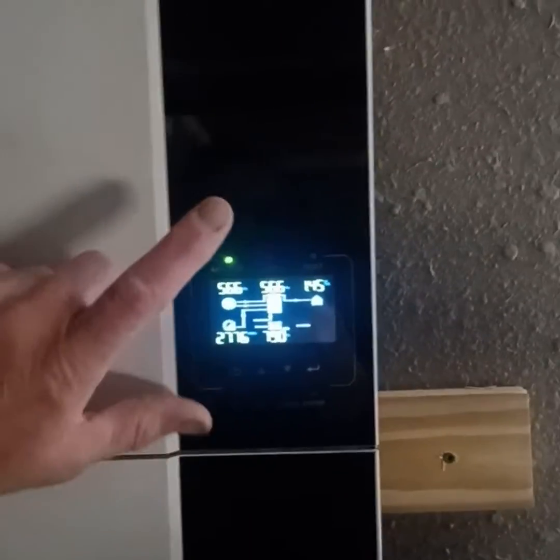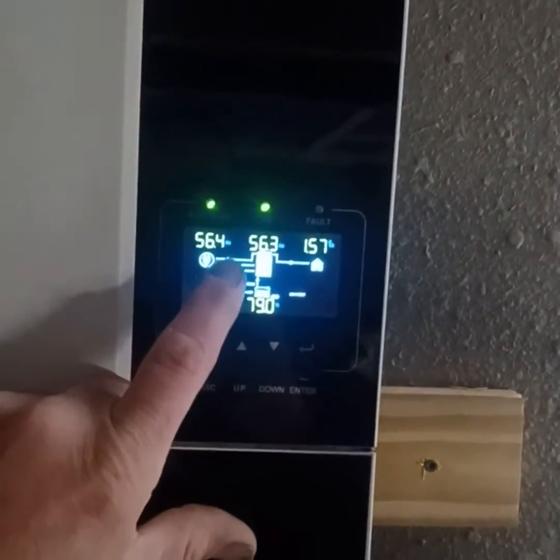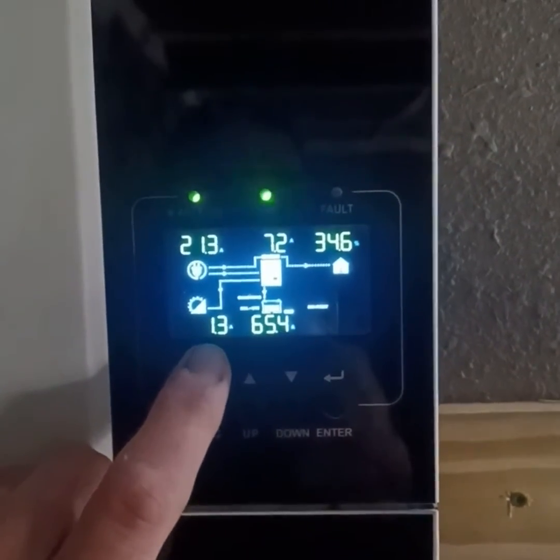Hey, what's going on? I got a hot tip of the day for the Growatt 5000ES off-grid inverter. The situation is that my generator supply line to this off-grid application is trying to overpower the solar, and the solar is only pushing 1.3 amps on this really crappy day, and we're trying to rob as much from the generator as possible.